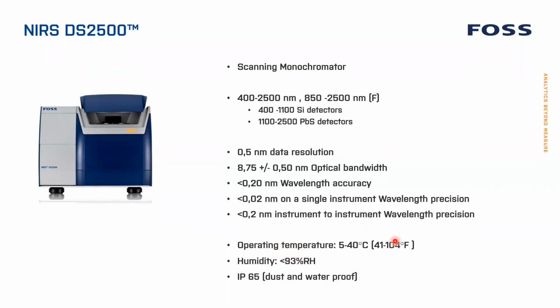Then we look at the operating temperature. It's from 5 to 40, which is normally much more than you will stand for a working environment. Humidity less than 93. That means it shouldn't rain. If it comes above this, you really have wet weather. And it's IP65, which means that the instrument itself is protected from dust and water. So you can pour water on top of it, and that doesn't make any difference. And it's completely sealed for dust as well.